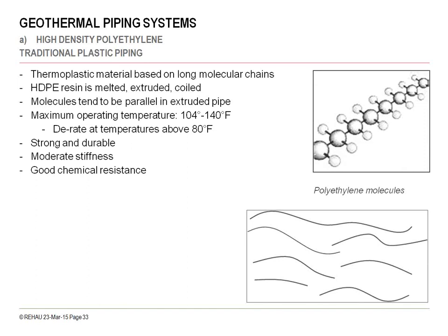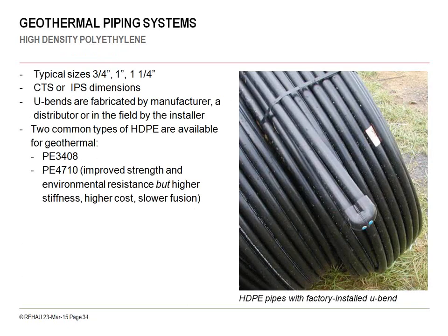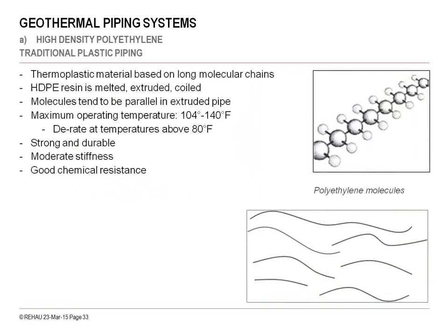It's strong. It's got moderate stiffness to it, good chemical resistance. The operating temperature of it is 104 to 140 degrees Fahrenheit. There is some slight derating that takes place on it over 80 degrees. What I want to point out is you can see that the polyethylene molecules in the piping material are free floating. So if you were to look at a piece of pipe, the molecule strands running along the length of that pipe would be just floating, if you will, and not being connected together.